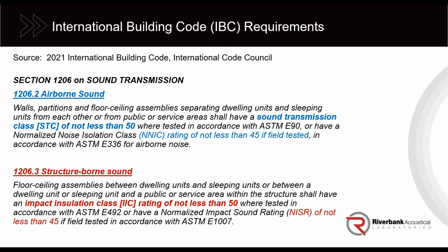Actually, that's not true. Oftentimes, a field test can be more challenging because there are a lot of factors that you can't control that could be influencing the test results. And we are seeing more and more where developers are being asked to provide both the lab test prior to construction and then the field test validation afterwards.